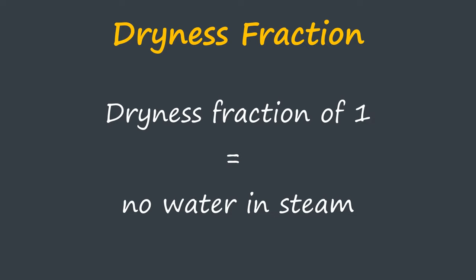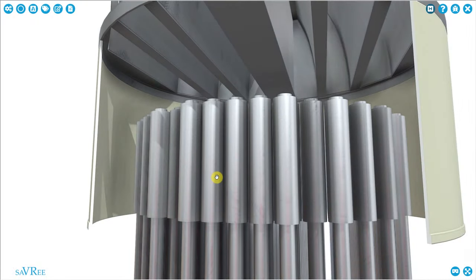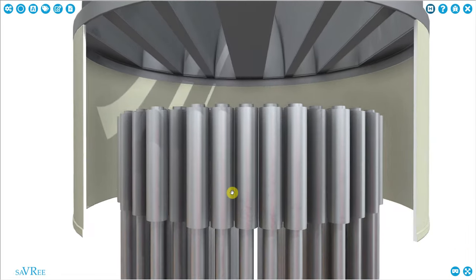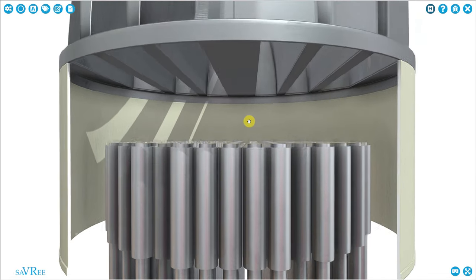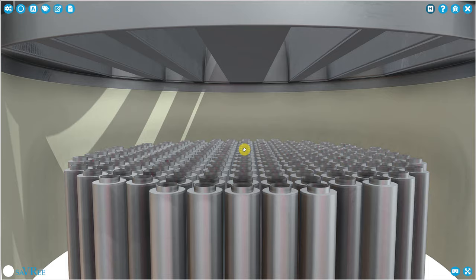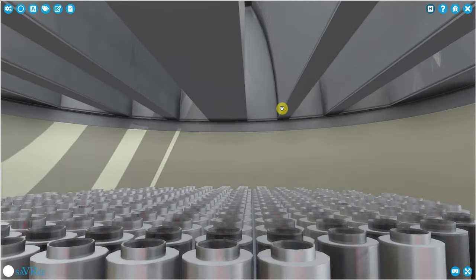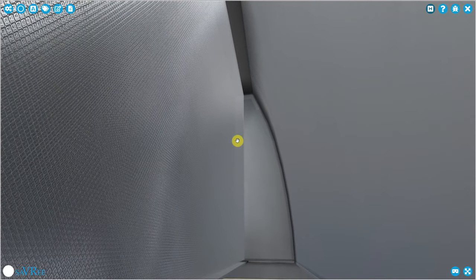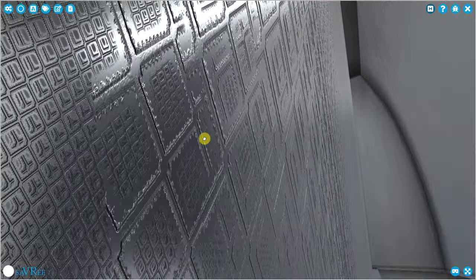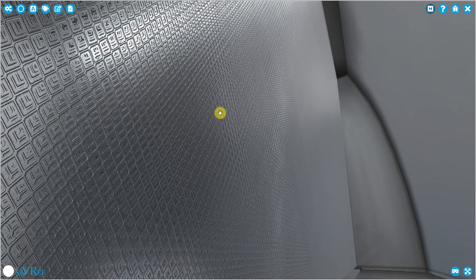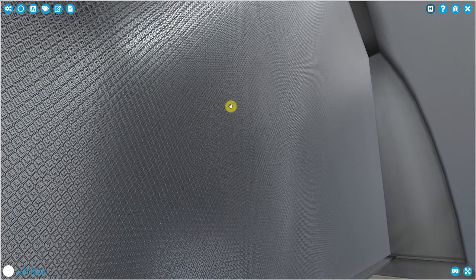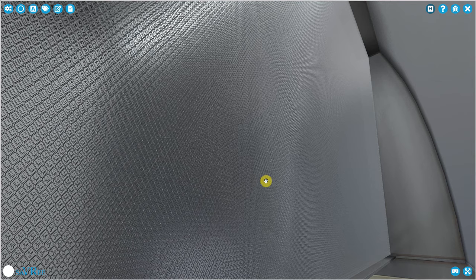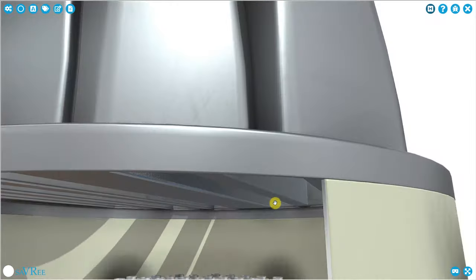The way we separate out the water from the steam is by letting it flow through a series of vanes that are within these pipes. And these vanes in part swirl the steam and the heavier liquid then condenses and begins to form on the outer periphery of these pipes. We can then drain off the liquid but allow the gas, the steam, to continue flowing through. Even when the steam flows out of all of these standpipes, it still then has to flow through our steam dryers and our steam dryers represent a tortuous flow path. You can see they've got this grid-like pattern here. This represents quite a hard flow path for the water molecules to flow through. Gas is much lighter and less dense so it flows through far more easily.